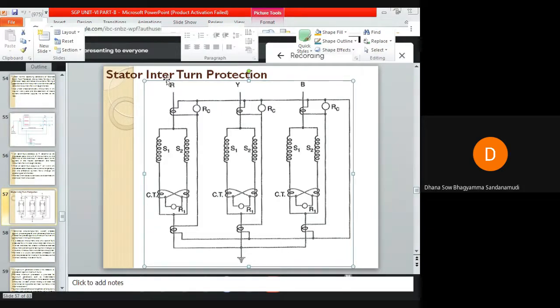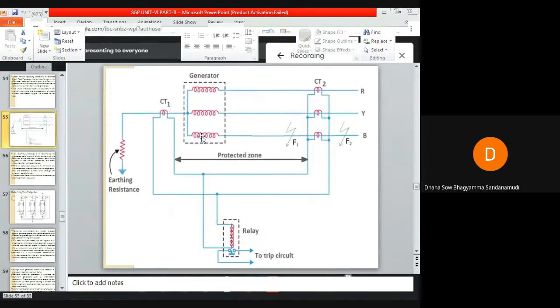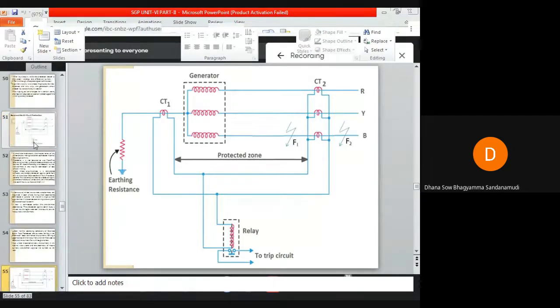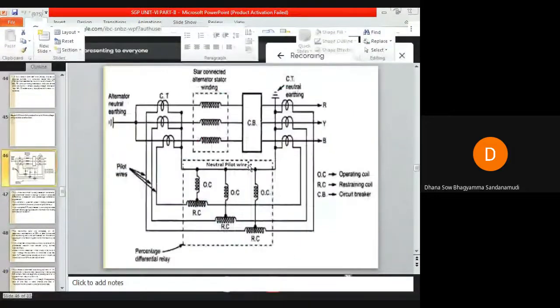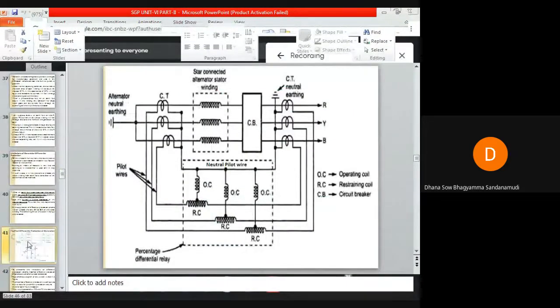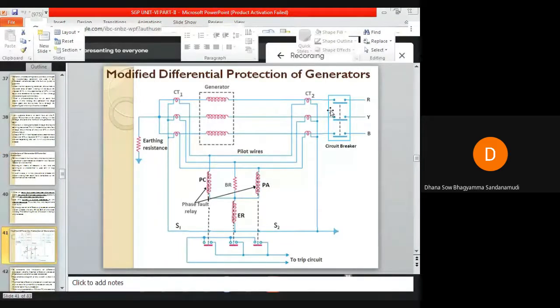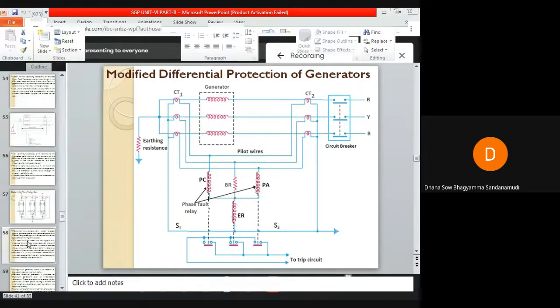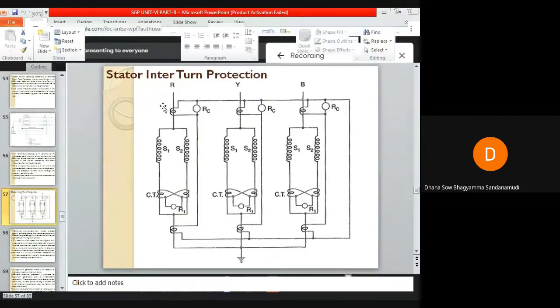If this is a single winding of phase R, on both ends of this winding we are providing CTs. That is our merz-price protection. These CTs are for merz-price protection. These relays will sense whenever an LG or LL fault occurs in the windings. Now, R1, R2, R3 are for stator interturn fault protection.